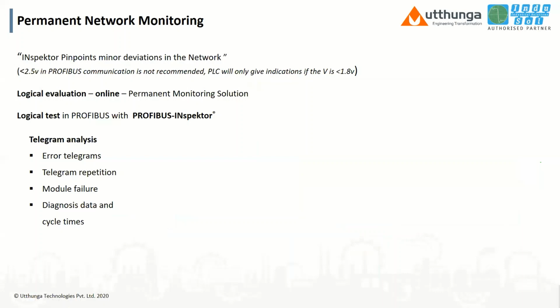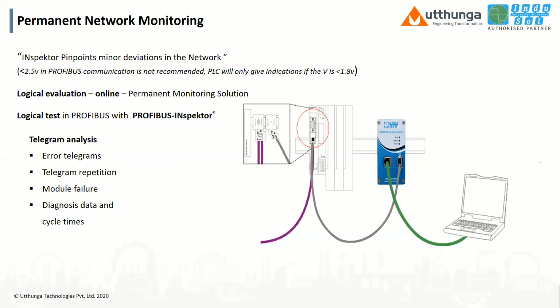So how do we find the problem, and how do we see exactly where the problem is in the network? What we are providing is a permanent network monitoring solution: PROFIBUS INspektor, our solution to find the exact problem and pinpoint the error in the network. PROFIBUS INspektor captures all active devices in the PROFIBUS network and displays them in a web interface. It's a web-based device, and moreover it is a passive monitoring device. Passive monitoring means there is no need for any interruption in the network. If it is a running plant, we can connect passively.